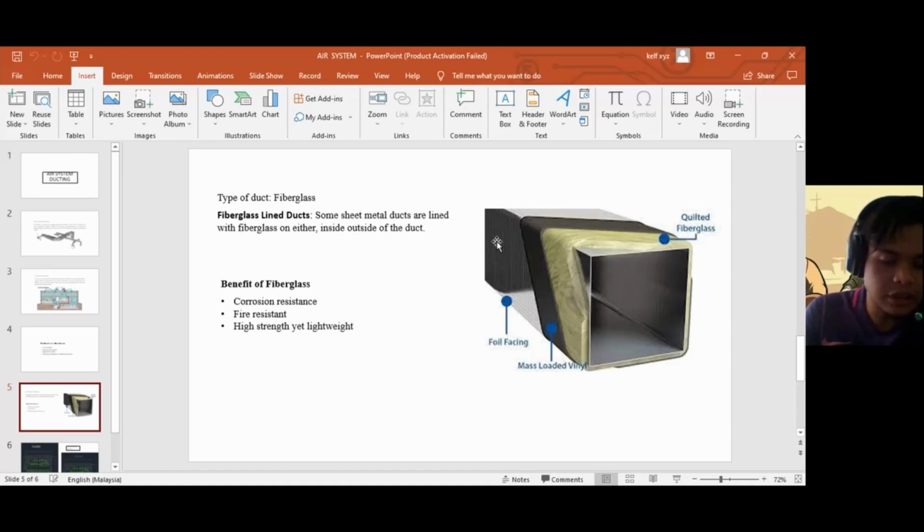The benefit of the fiberglass is that it is corrosion resistant. Fiber reinforced duct is specially designed to withstand the harsh underground environment. Our FRP duct stands up to water temperature, charge, and acid soil conditions. Second is fire resistance. All surfaces of the duct and fittings, as a finished composite, meet the flame and smoke requirements of a Class 1 duct per UL 181 and UMC 1 to 10.